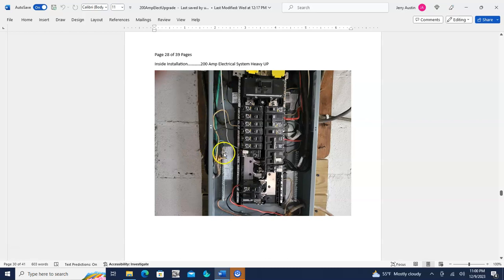This shows that green wire safety ground hooked into the ground bus here. This is the safety ground bus over here. This silver one right here, this is the electrical ground bus. And once again, these are your circuit breakers here, and you can see the black wires are hooked into the actual circuit breakers. The electrical neutral wires are hooked into this electrical neutral bus here, which is the electrical ground bus. And these two safety ground buses, you've got one on each side, one there and one here, and they're connected together, as you can see, with this big solid copper ground wire. They're connected together right on the very bottom there.